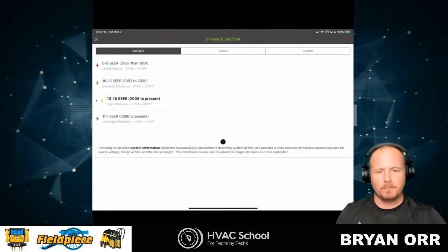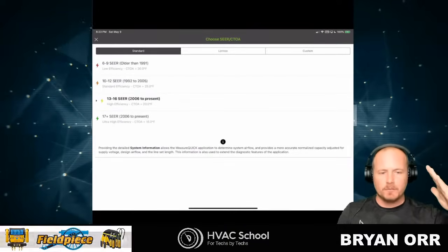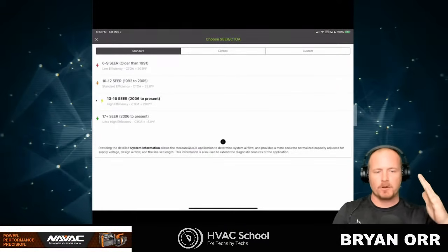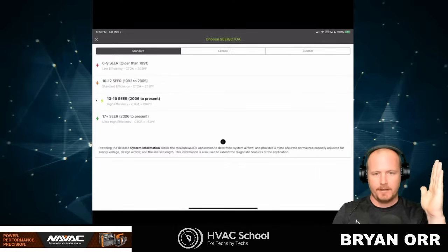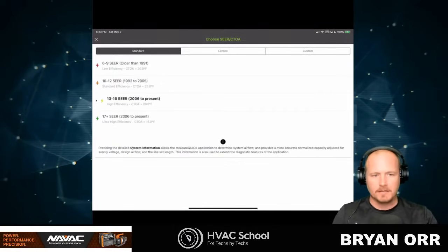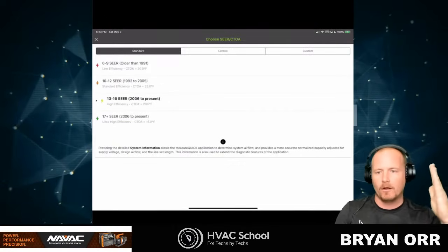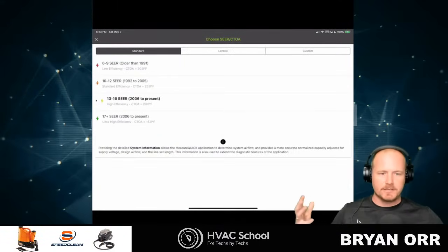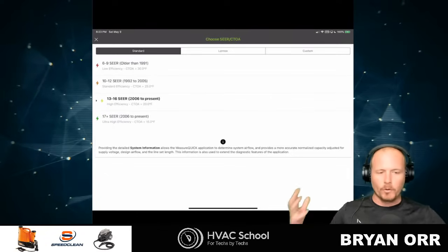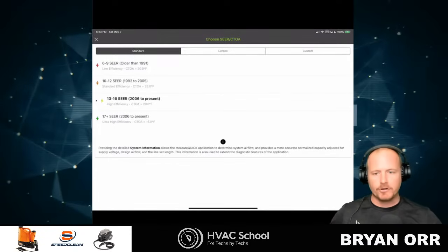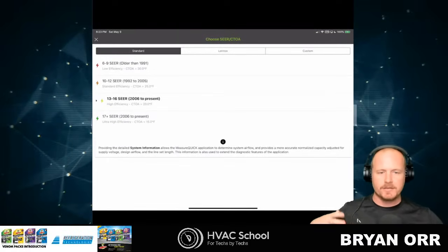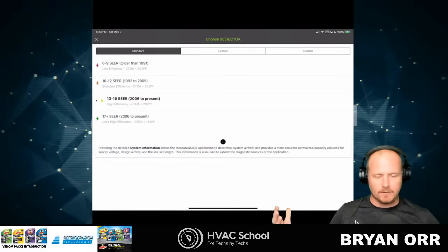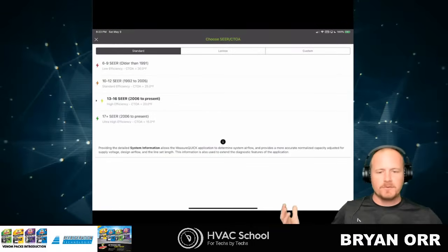Yep, and that's the point, is that once you hit that benchmark, once you've benchmarked it, now all of your ranges move to the center, basically. And they're going to now track with changes in ambient conditions or changes in system load, accordingly. And that's a really nice thing. And so you're not now using guesses. You're comparing the equipment against itself, which we've all done. We've all done this for years.